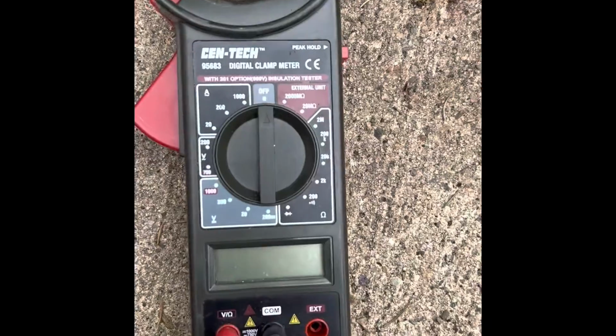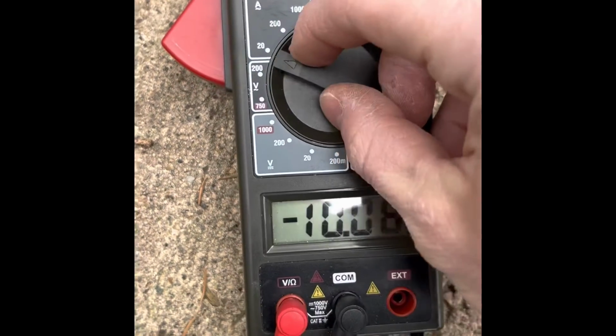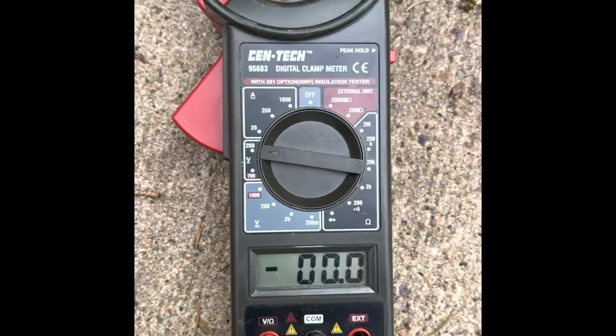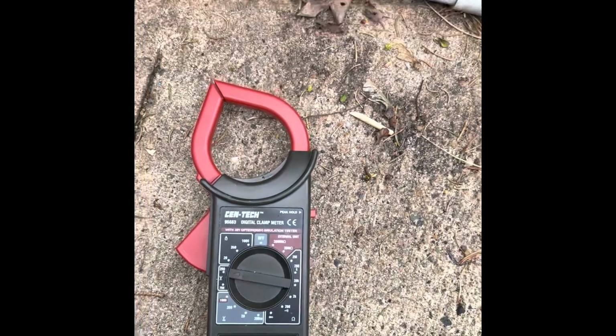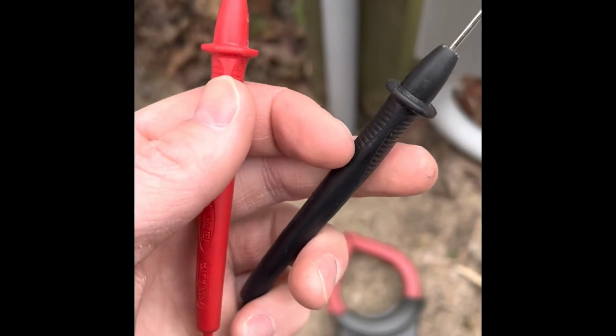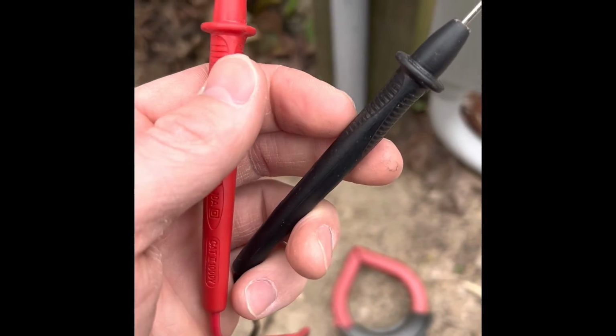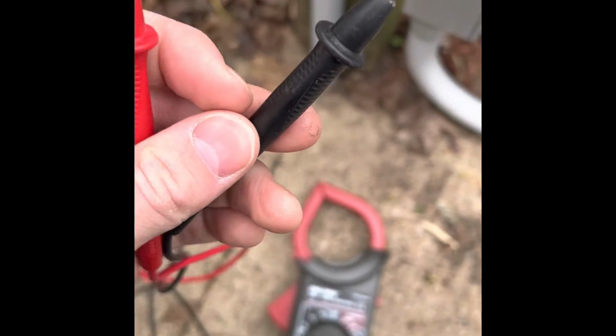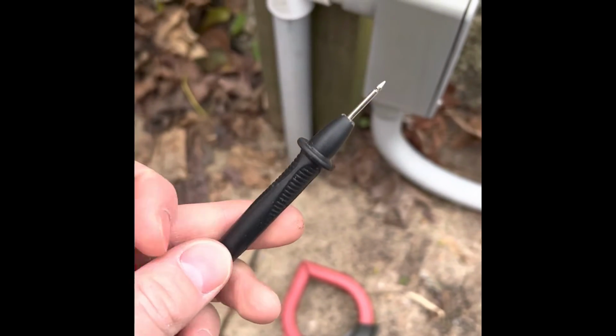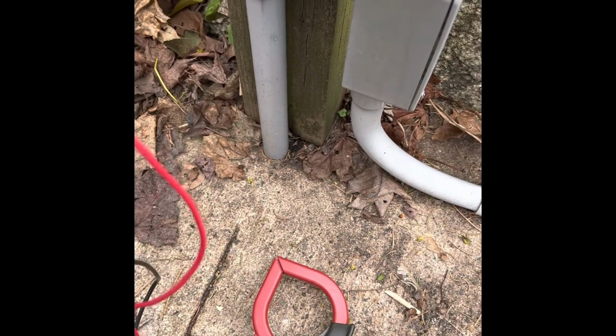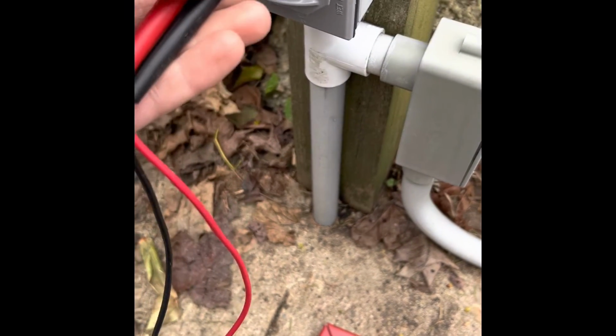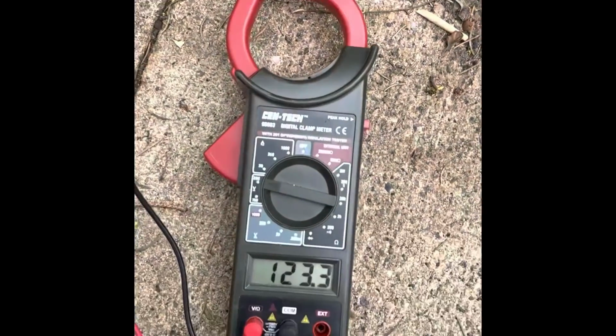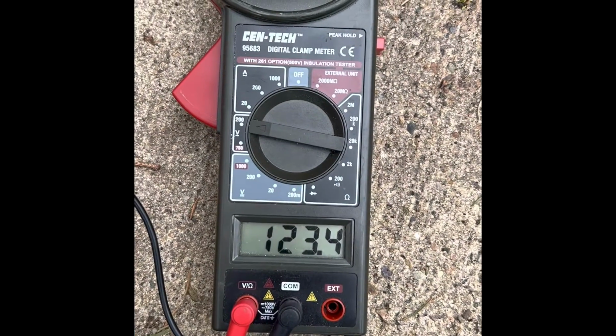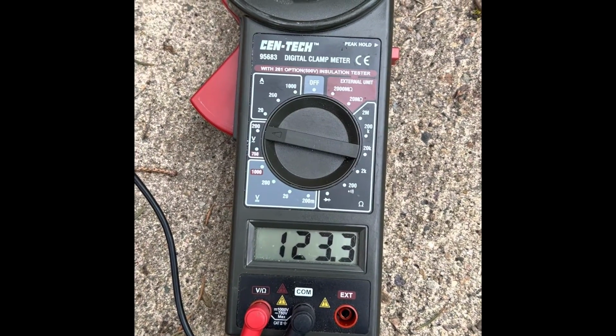So I'm going to set my meter to AC 200 because that allows us to measure up to 200 volts. I'm going to take the red probe and put that to the hot side of the outlet, and I'm going to take the black probe and put that to the common side of the outlet. And my reading is 123.3 volts, which means that my outlet is live.